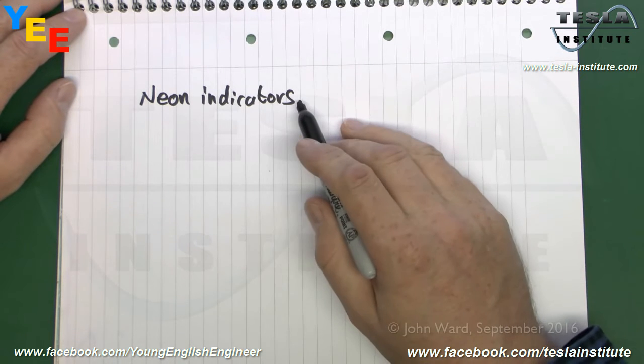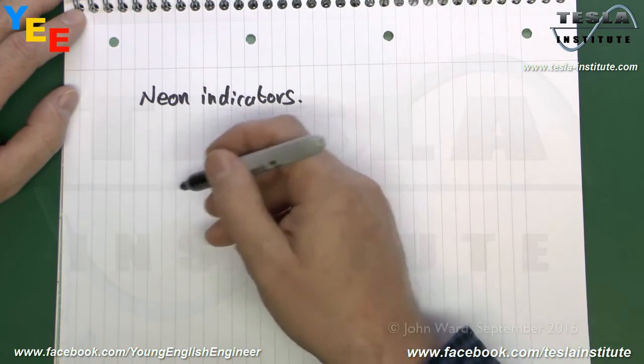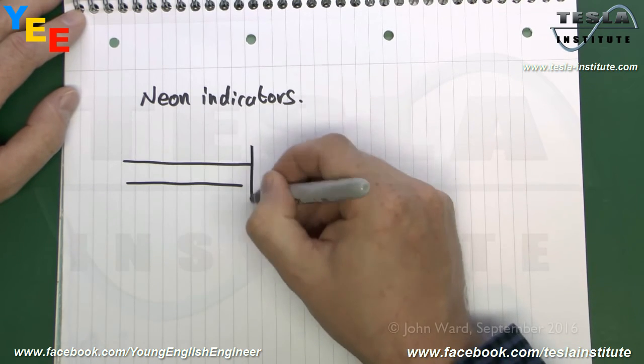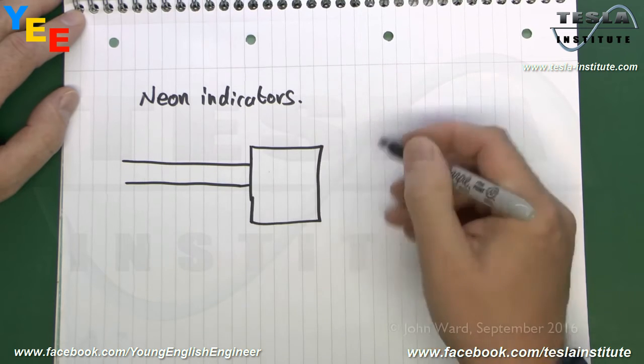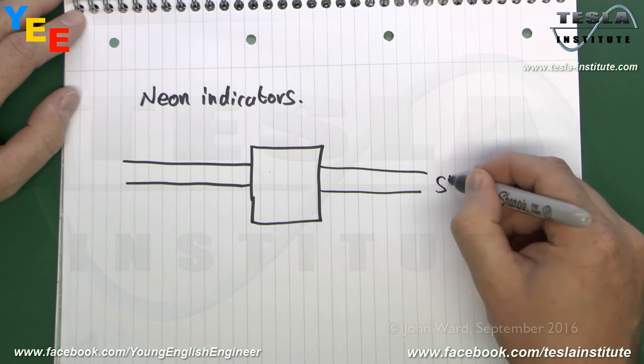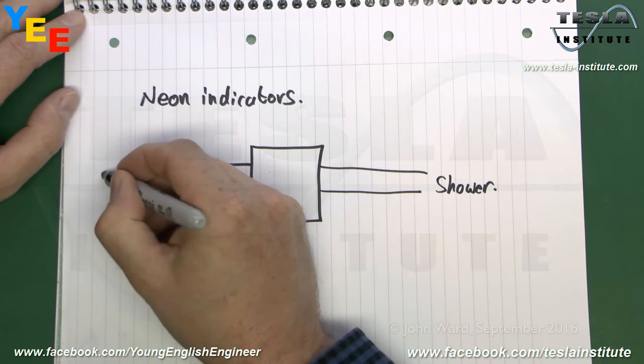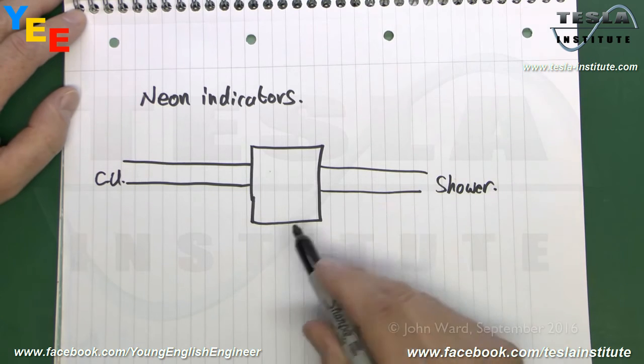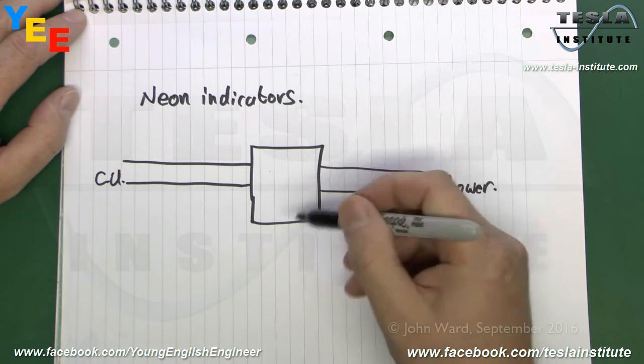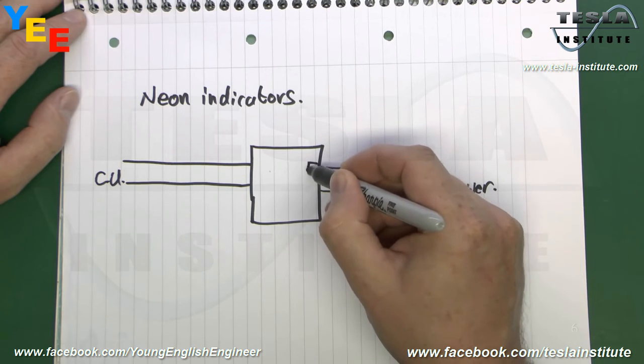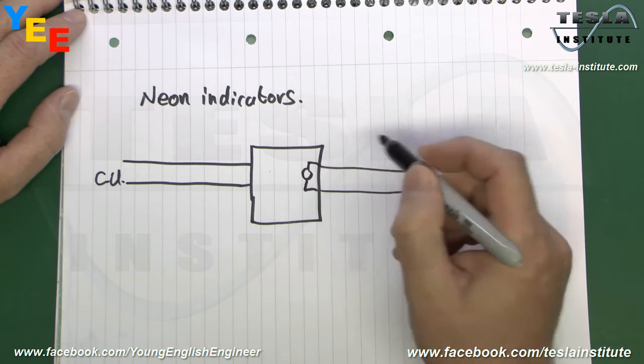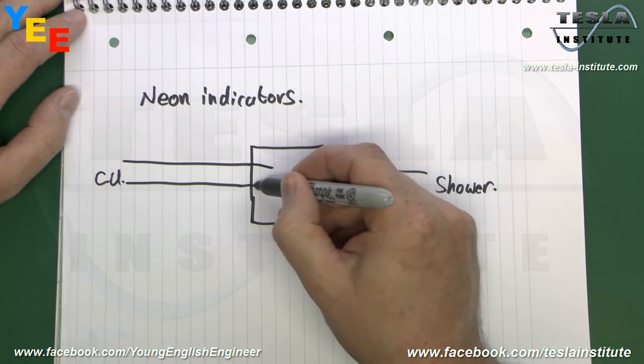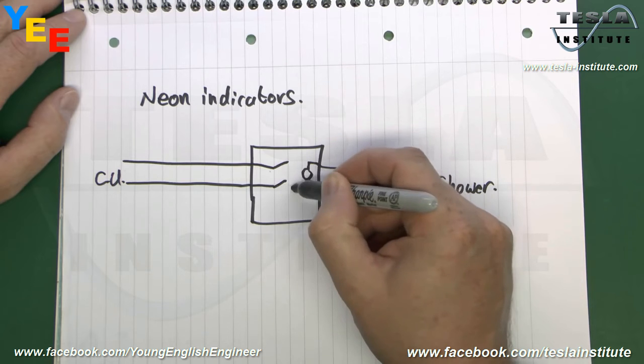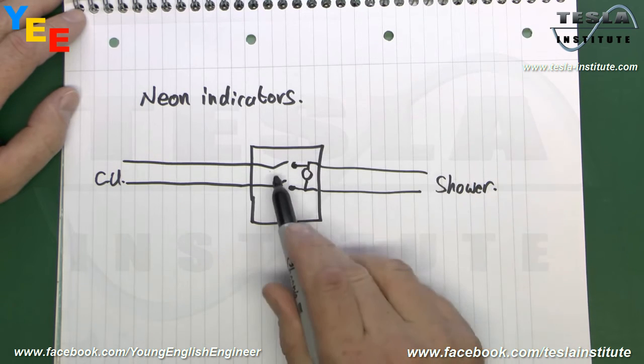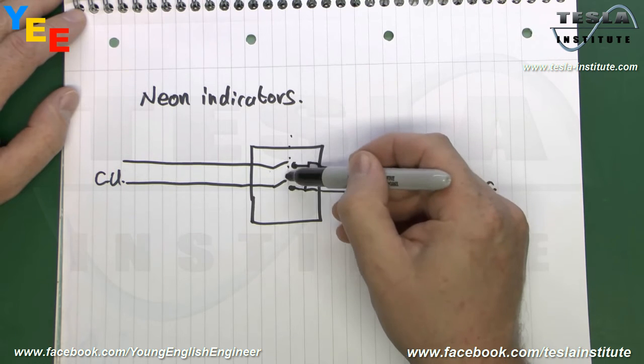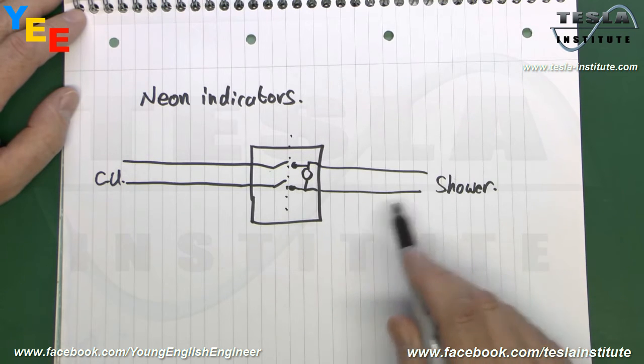Now, normally these are fixed on the load side of the switch. So if you have your circuit wiring coming in, and then you have your switch here, and then you have your wiring going out, say to the electric shower or whatever, and this would be the consumer unit at this end. Normally, when the switch is in the off position, the neon indicator is over here, and it's basically wired between the line and neutral on the load side. So if the switch is in the off position, you're only testing up to this point here, and the neon is part of the actual load, as it were, so that's fine.